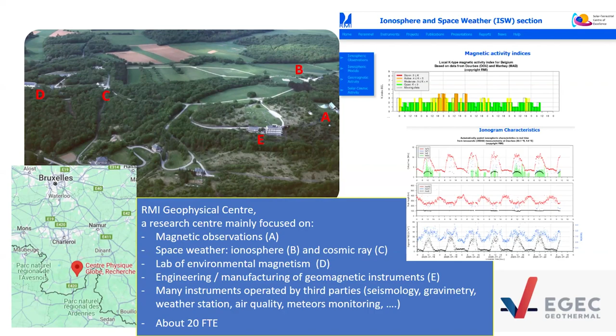So to introduce the DI flux, I will first explain briefly why this instrument, what is the reason for this instrument. As you know, the Earth's magnetic field is a vector, and a vector which is both spatially and over time really changing. So in magnetic observatories, which are at fixed locations, we measure 1 second data. And this is performed by means of a variometer, to perform the vector measurements every second.